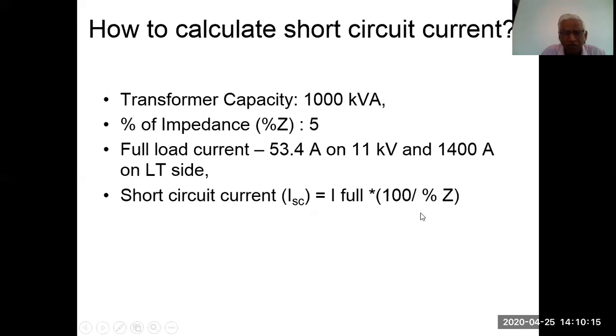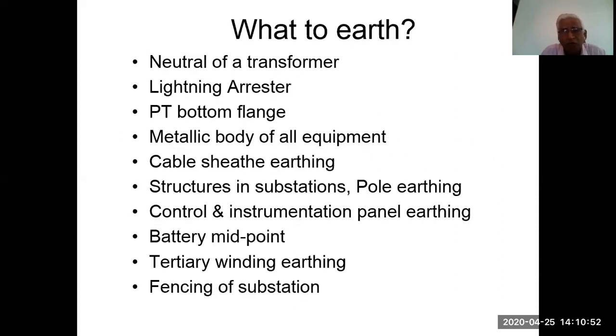When Z is 5, 100 by 5 is 20. So the current will be 20 times the full load current. Full load current is 1.4 into 20. That comes to 28 kiloamperes, the short circuit current flowing through this. This 28 kiloamperes will go to the relay through the CT, and the relay will give an indication. The circuit breaker will trip and isolate the transformer, or the load from the transformer.